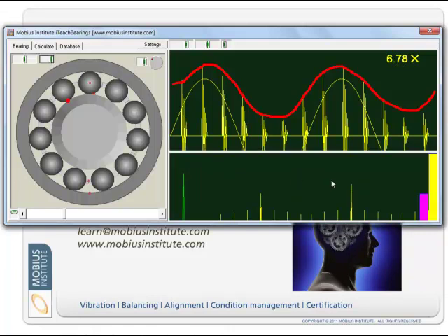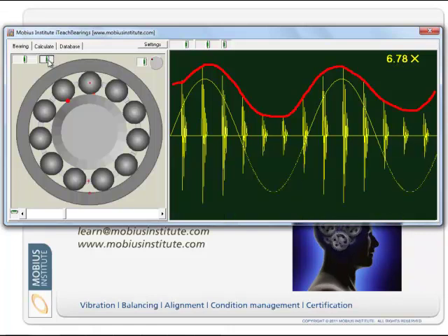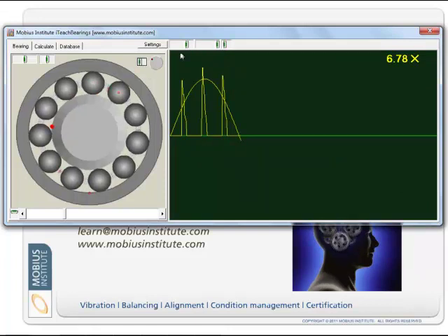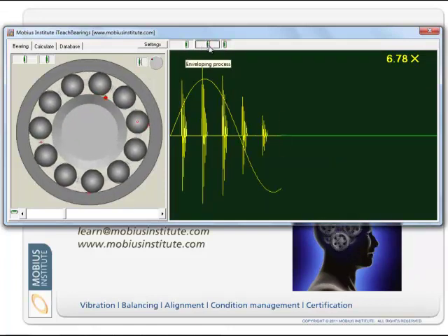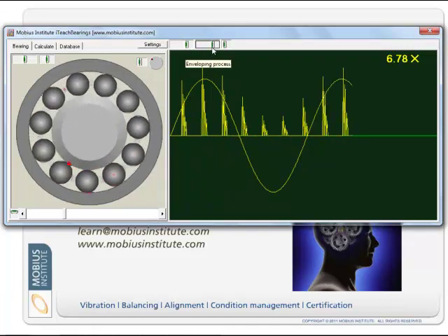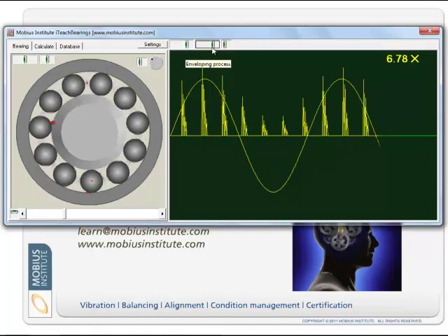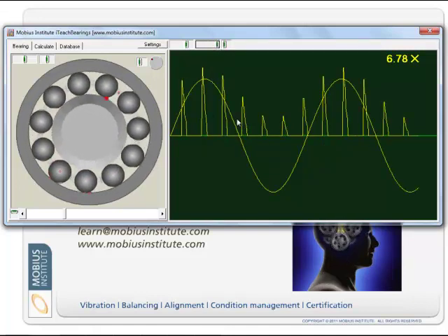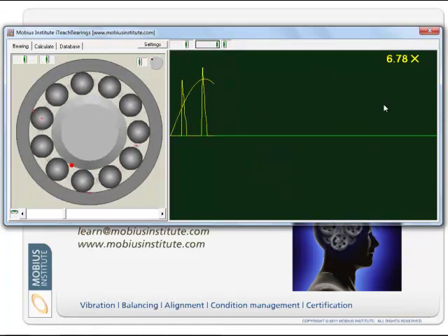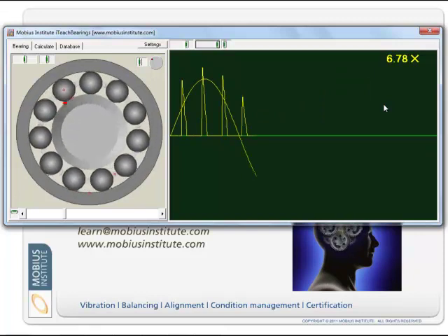There are other things we can do — we can look at spectrum analysis and overall level readings as well. We can do all sorts of things demonstrating how the modulation process works, the demod process. In this case, we've filtered away the low frequencies so now we've only got the bearings, and we rectify it so that the negative is all positive, then we envelope it — and there we go. And if we do an FFT of just that, that's what you see in an enveloped or demod spectrum. That's where those techniques work.